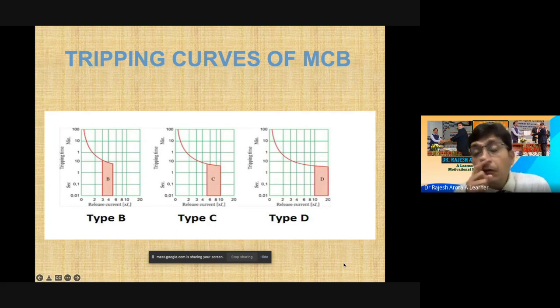And be careful, there are 2 tripping mechanisms within the MCB. One is overloading, and the second is short circuit. The third important factor is the short circuit current capability of that MCB: 10 kiloampere, 20 kiloampere. Where you have to use MCB, where you have to use MCCB, where you have to use ACB. How to select your wire, class B, class 5, plays a very important role.